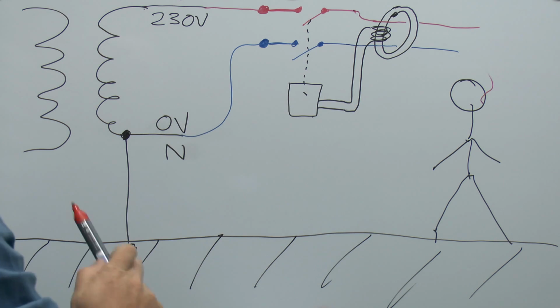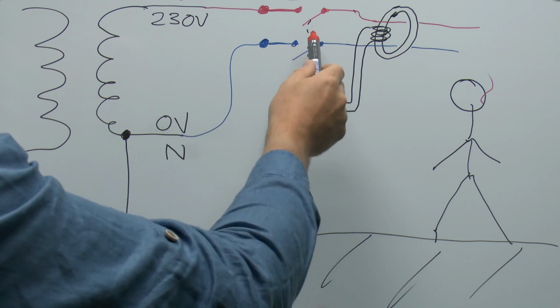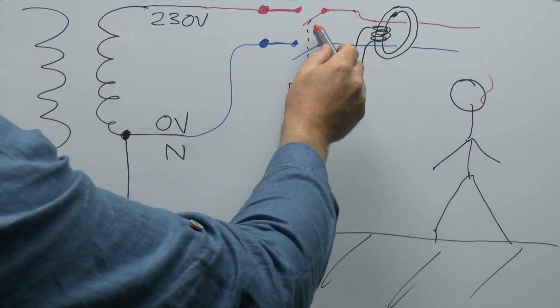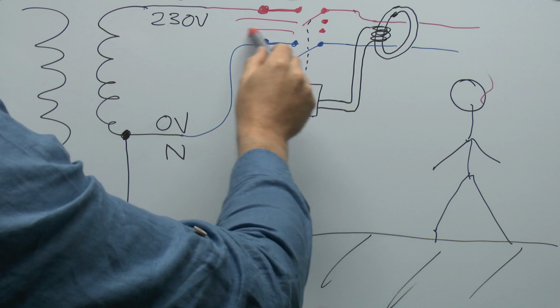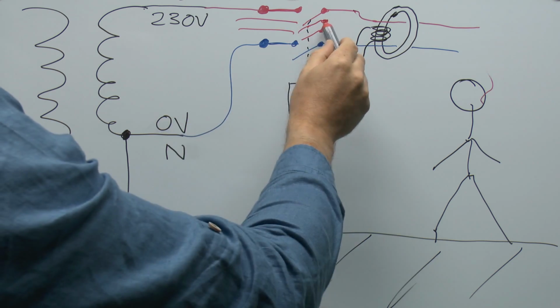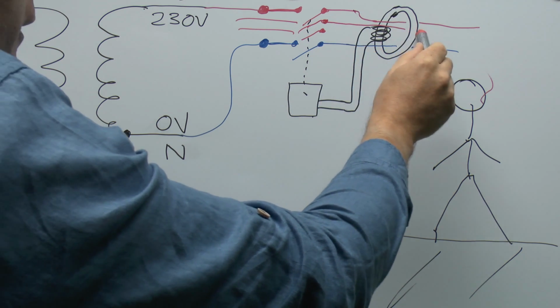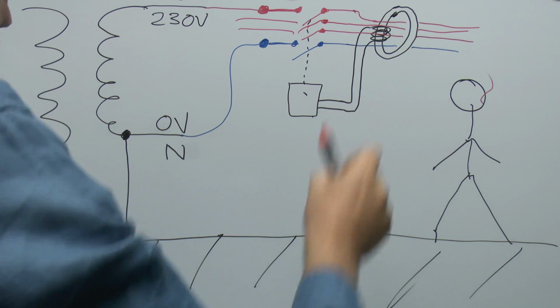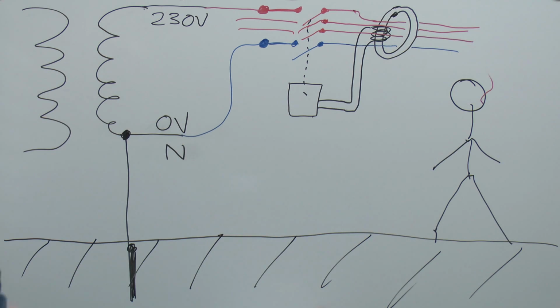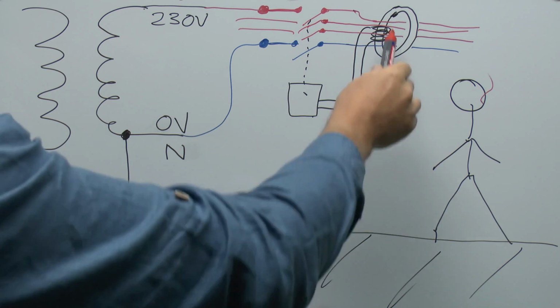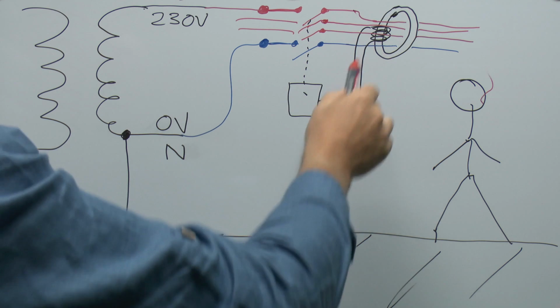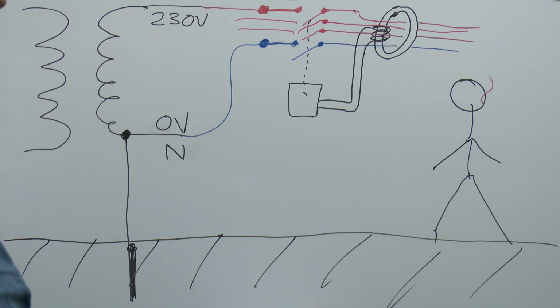This can easily be extended to a three-phase device, or with three lines coming in. All that happens is you've then got the two additional conductors there coming from the supply. There'll be an additional two switch contacts, and then all that happens is that the additional ones simply go through the centre of the magnetic core along with the rest of them. So it's simply monitoring the current across all four conductors, and again it works in exactly the same way. If there's any kind of imbalance, that is detected here and of course will trip the device.